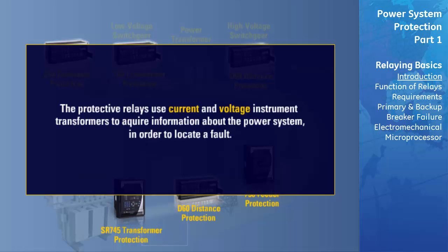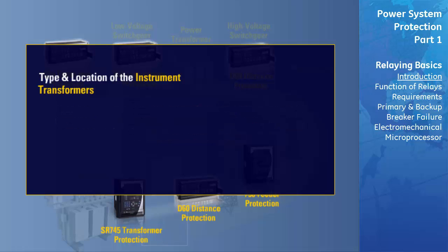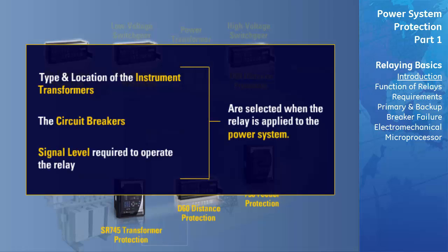The protective relay uses current and voltage instrument transformers to acquire information about the system, such that a fault can be located. The type and location of the instrument transformers, the circuit breaker which is to be tripped by the protective relay when it operates, and the signal level required to operate the relay is selected when the relay is applied to the power system.